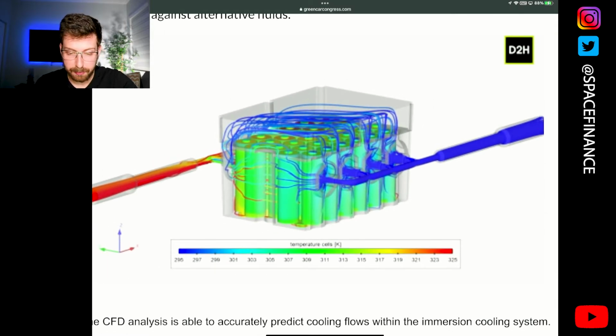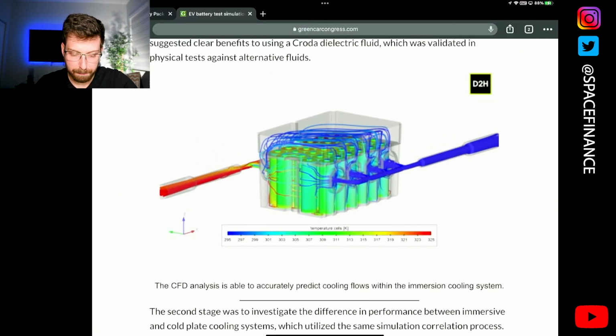This, in my opinion, is what we see with immersion cooling: it's essentially wrapping around and having everything in a dielectric fluid, which flows in from the inlet on the right, flows around it, then exits through the outlet picking up all that heat. The heat pickup, as you can see, is around 40 degrees.